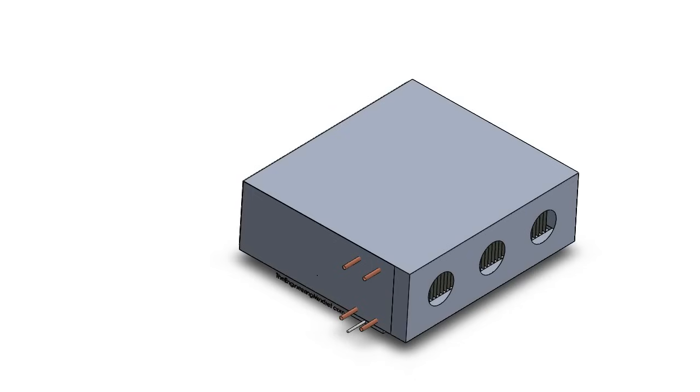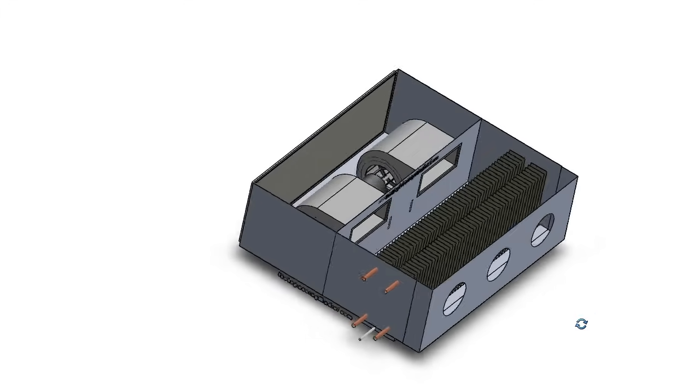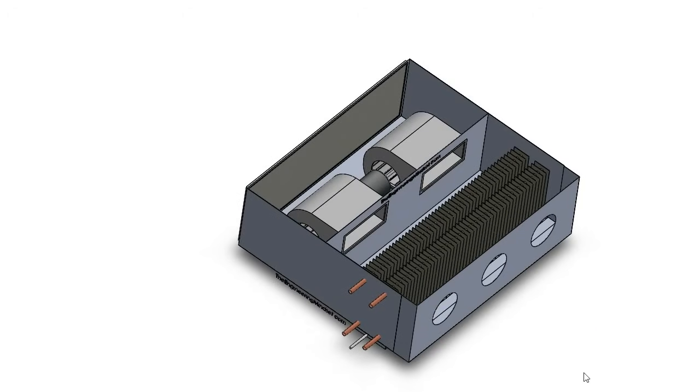Let's have a look inside a fan coil unit to see its components. If we remove the lid, we can see it's actually fairly simple in design. This is the air inlet — air comes through this face here. This is a removable filter; the filters look something like this and can just be pulled off, then cleaned or replaced. They're there to stop dust coming in, as that air is going to be sent out through the local ductwork around the office.